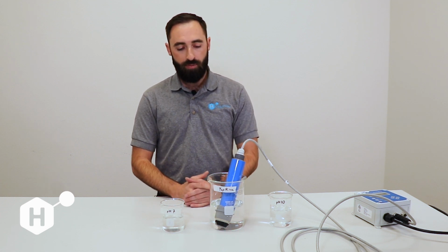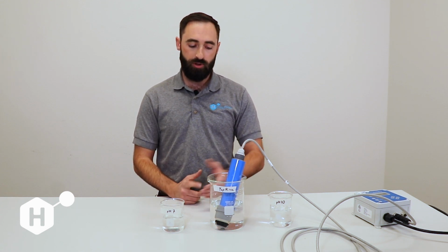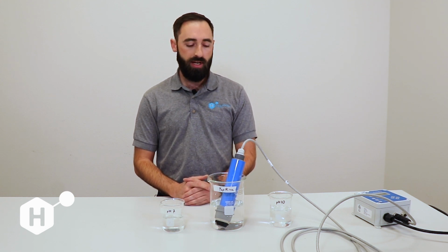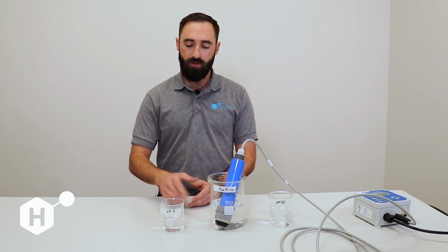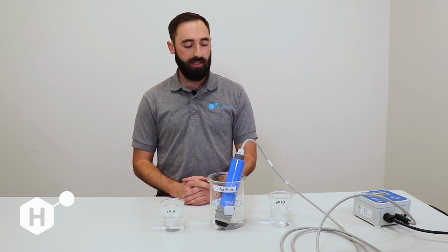You're going to want a tap water rinse solution. This can just be filtered tap water out of the sink. It can also just be bottled water, or ideally you can use deionized water. But it's going to be whatever you have available to you. Really all we're going to use that for is rinsing between pH buffers, just to make sure that we're not contaminating the next buffer that we'll be doing the calibration in.